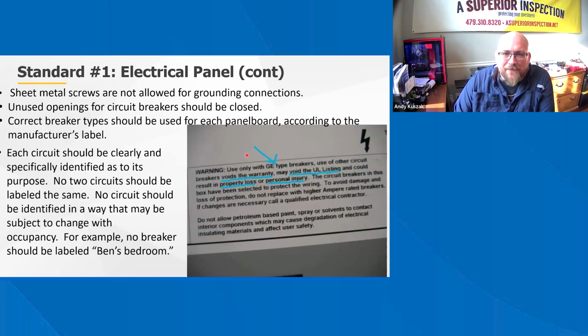So just real quick, again, with flippers or homes that are existing or have been around for a while, a lot of times you are going to find different manufacturers' breakers inside of a panel. So there is a lot of controversy with that statement. You'll find if you call something out like that, you'll have one electrician who will agree with you and say, yep, we need to replace all these breakers. And then the next electrician that comes out is going to throw you under the bus and say, no, it's totally fine. There's nothing wrong with it. They're all UL listed. So definitely we are always on the side of the homeowner and doing what is the safest and the most proper process and installation. So calling out for mismatched breakers, it's our job.